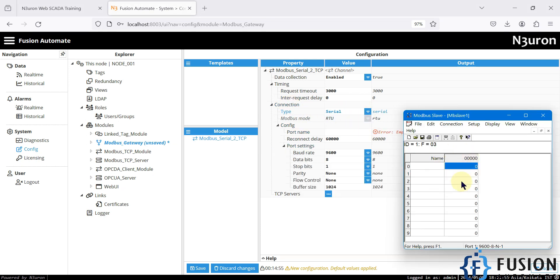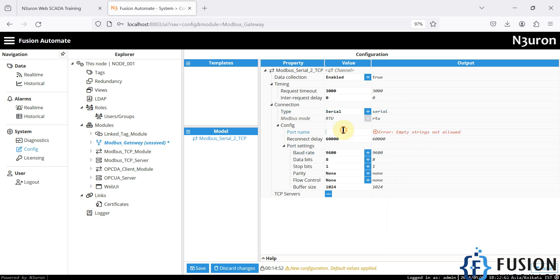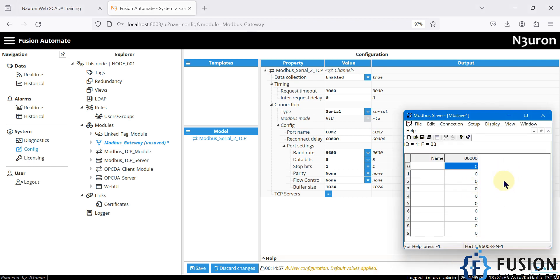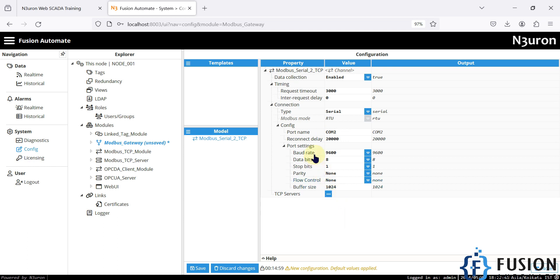First we have to connect Neuron with this Modbus serial device. In the connection type I'll select serial connection. The port name I'm going to use is COM2 — the Modbus slave software is on COM1 and its data is redirected to COM2, but only one application can connect to a COM port at a time. So Neuron will take control of COM2. I'll set reconnect delay to 20,000 milliseconds, baud rate 9600, data bits 8, parity none, and stop bit 1, then save.